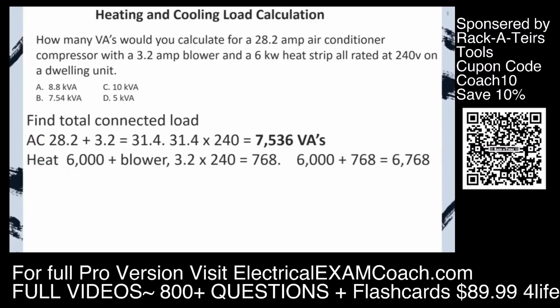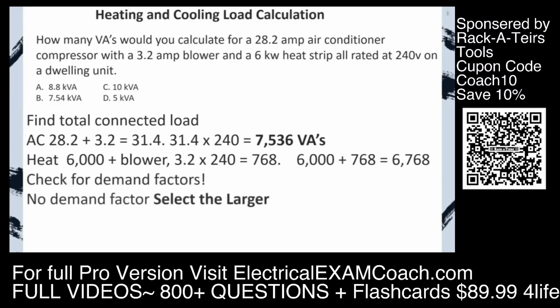We total those two together, and we check for demand factors. There are no demand factors on this part of the code, so we're just going to select the larger, and in this case, we're going to select the cooling. Great job.